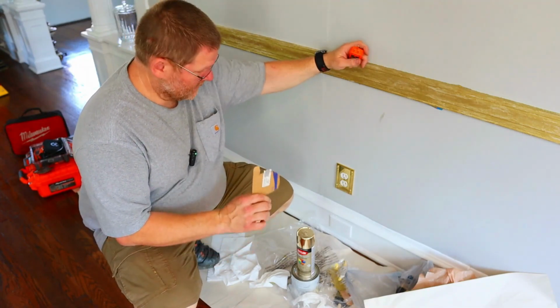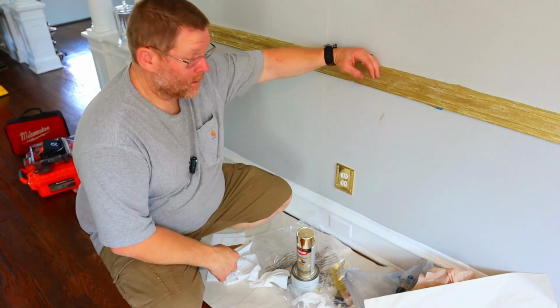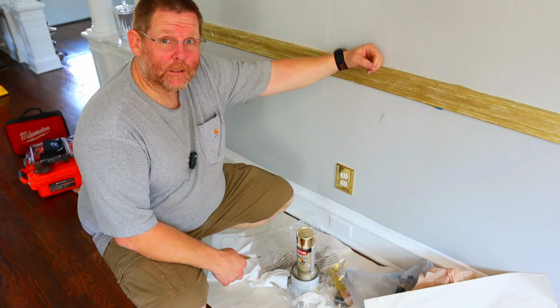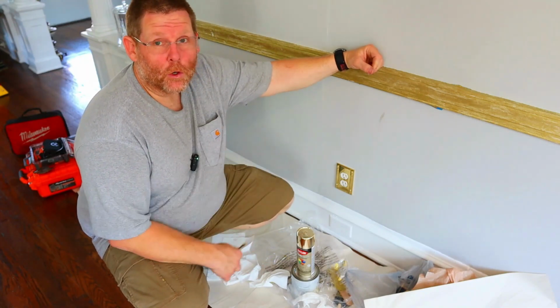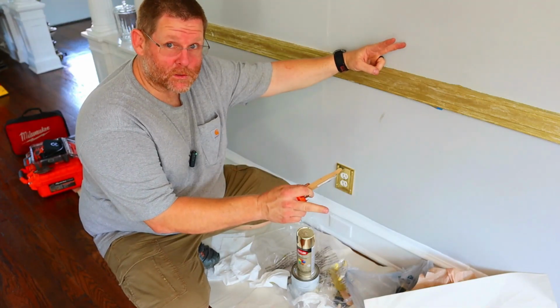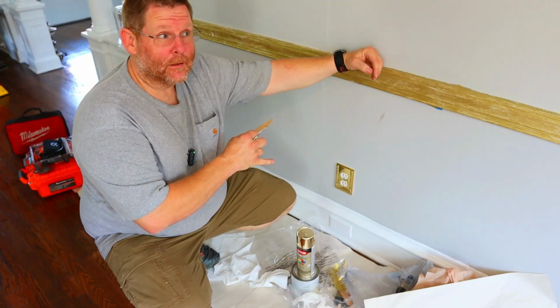And luckily, even though they did rewire, because there's a little box here that used to be a receptacle, and they moved it up, they didn't bootleg the ground, because they easily could have, and then nobody would have known. But they were honest, and they did it the right way, almost. So we're going to show you later in this video how to fix that so it's safe.